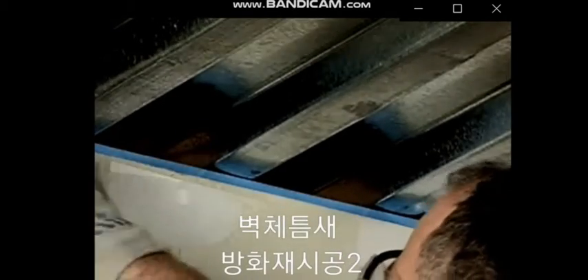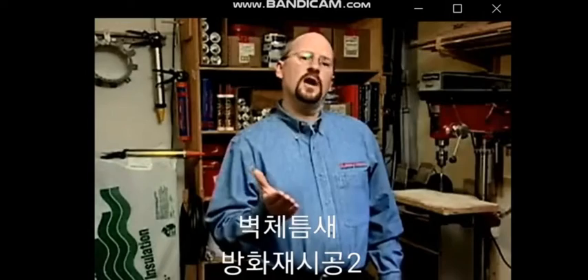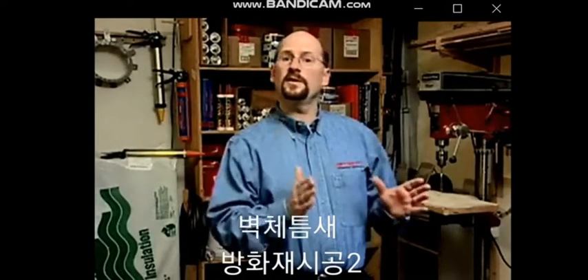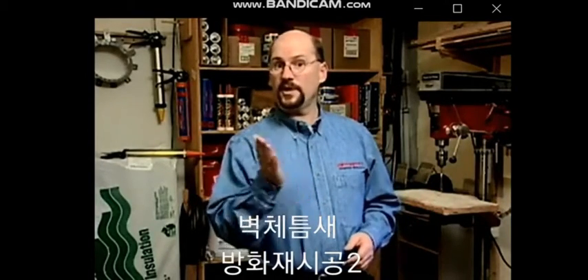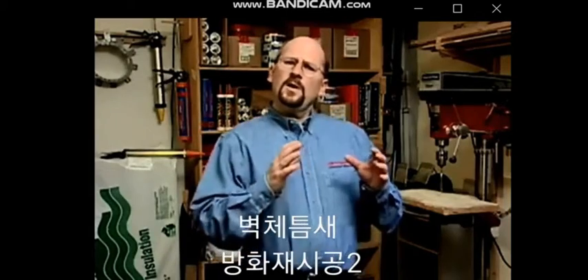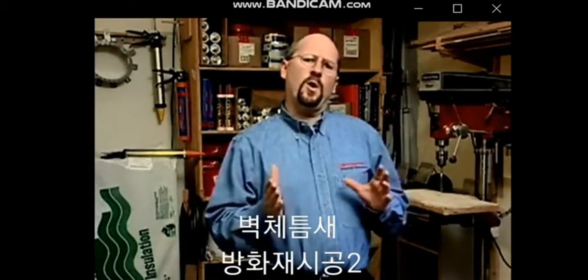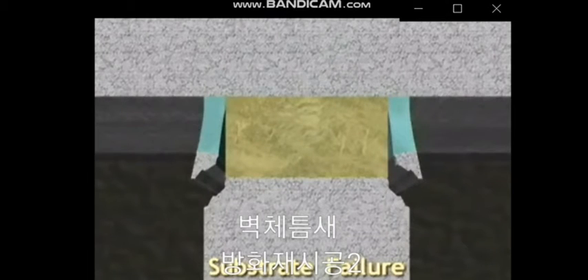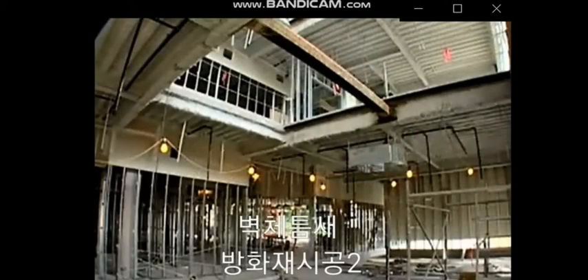before installing the sealant. The final cause of sealant failure really isn't failure of the sealant at all, but of the surface that it's bonded to. When a fire stop seal is bonded to a wall or floor that's damaged or weak, the seal will hold, but will pull the substrate apart when the joint moves. This is called substrate failure. A common example of substrate failure is old spalling concrete.